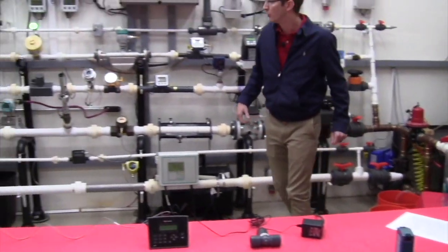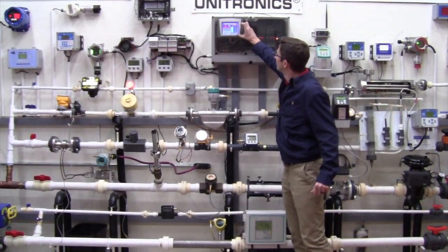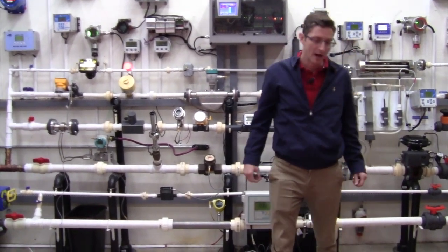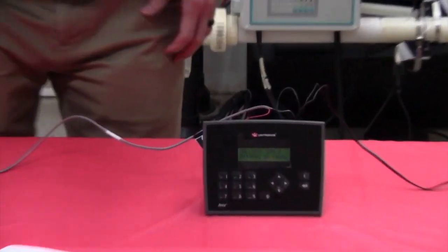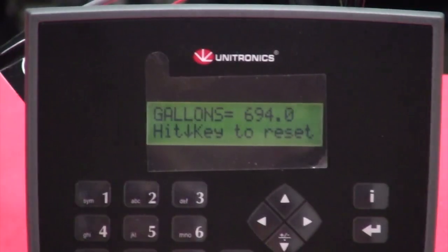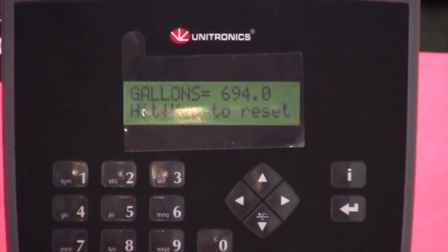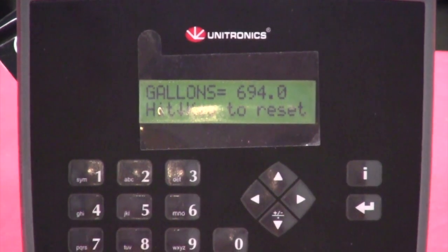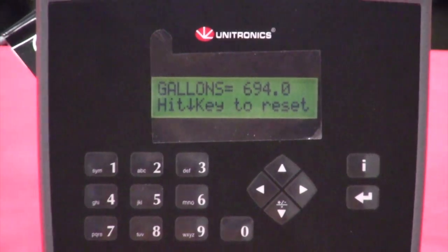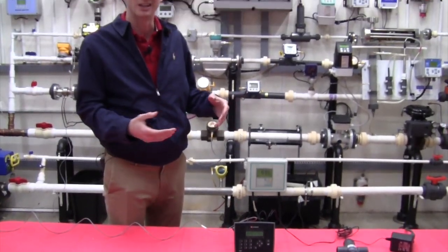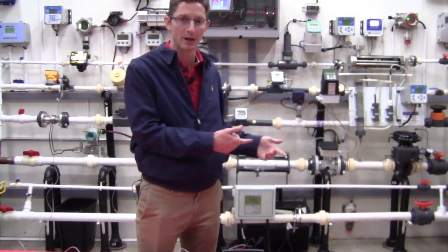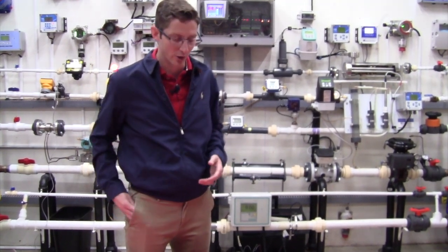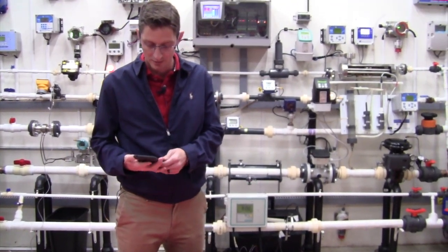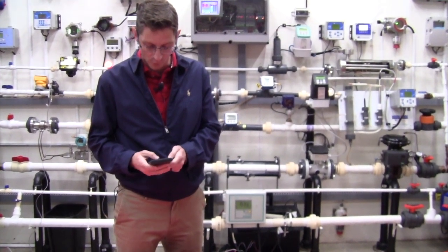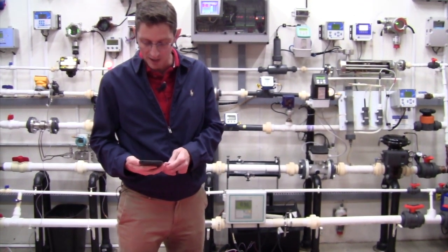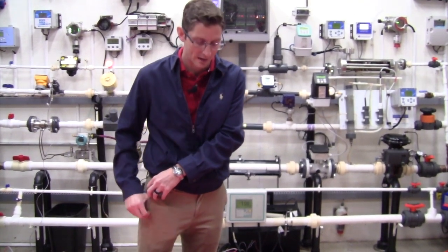All right, we've now finished flowing our 5 gallons. Turned my pump off, closed my valve. We come back over to the display and we see how many total pulses we've counted. In this case, it is 694. Since I know that I have a 5-gallon bucket, I take my total number of pulses and divide it by the volume of the bucket that I'm filling up, and that's what my K factor will end up being. So in this case, 694 divided by 5, my K factor needs to be 138.8.